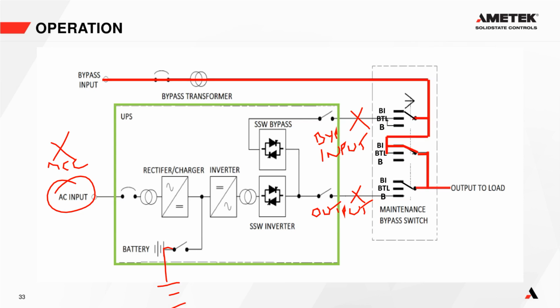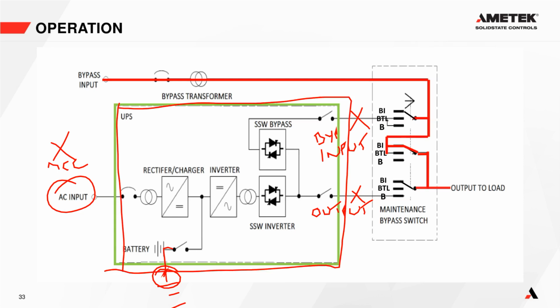Let's see, the battery is external here, and there is a disconnect. We can lock out, tag out that battery disconnect. That allows us to make this whole UPS cabinet volt-free, so we can do intrusive maintenance and clean it out.